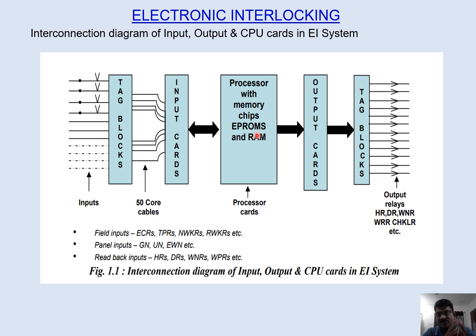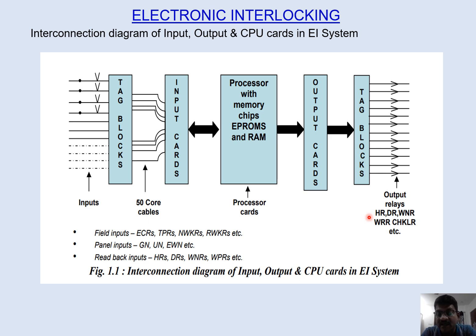After processing, based on the interlocking and the station-specific application logic, we have output cards which are connected. These output cards give output to pick-up relays through a tag block. Examples of output relays include HR, DR, point operation relays, crank handle relays, and all such things which are output relays.